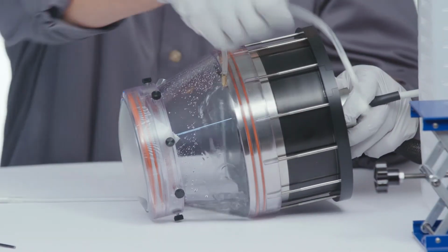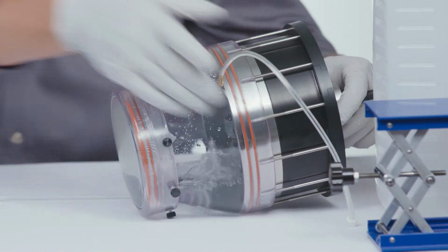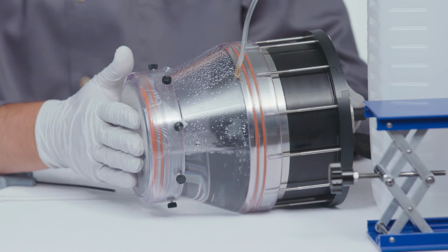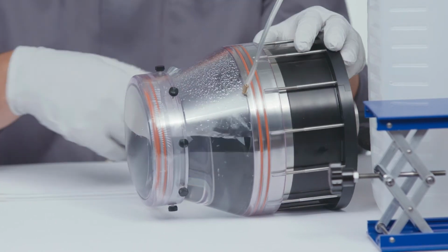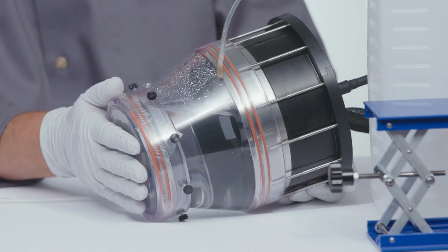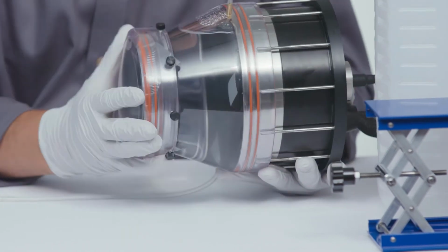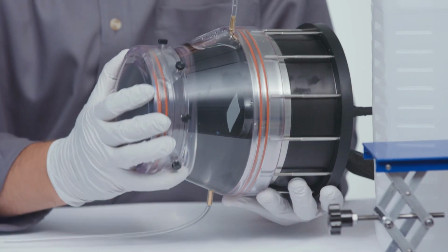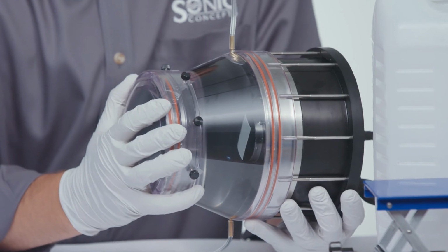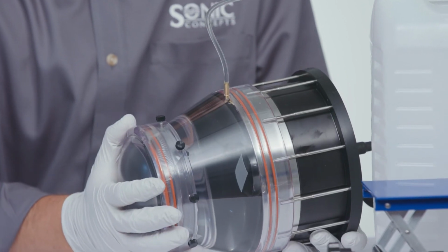During filling, it's advised to push the water-filled membrane flush to the exit plane of the coupling cone to sustain equilibrium. Be sure to evacuate any bubbles by lightly tapping the exterior of the membrane or cone in the proximity of the bubble. The slight shock should dislodge the bubble and seep through the out tube.